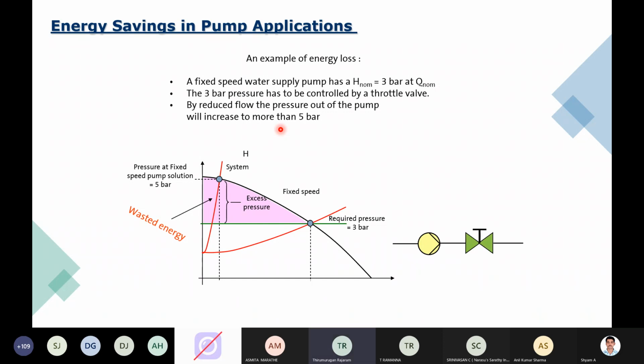So in terms of energy saving in pump applications, what I can reflect here is a fixed speed pump with a throttle valve. For example, you are operating with a flow of, say, 80 meter cube, and suddenly your demand drops and you want to operate at 20 meter cube. The system will operate at this head, where you can find excess pressure getting into your system. Your system has been designed for handling 3 bar, but unnecessarily you will be giving 5 bar pressure into the system. This excess pressure will impact a lot of things in terms of wear and tear in your pipes. It can impact your head calculations. And moreover, you will end up with very inefficient operation.